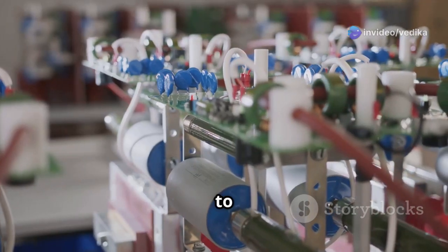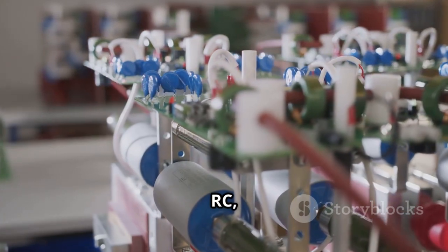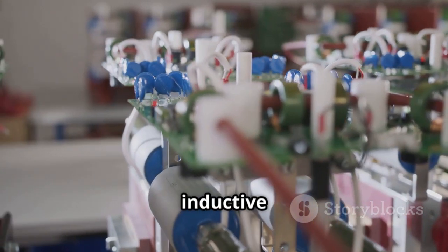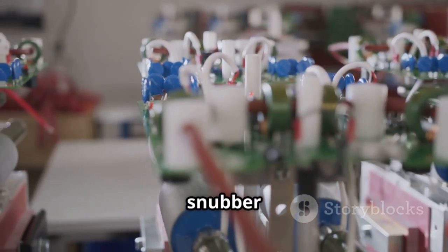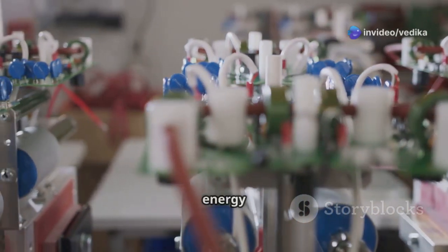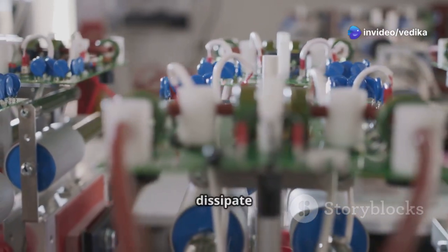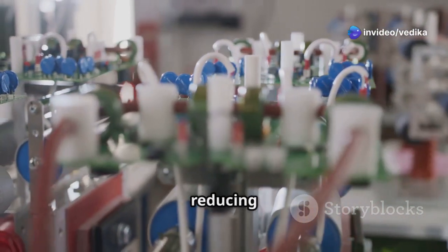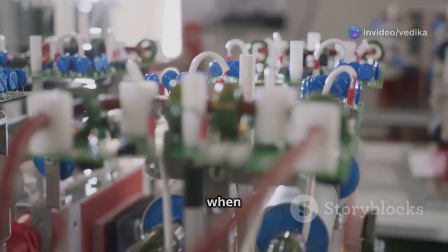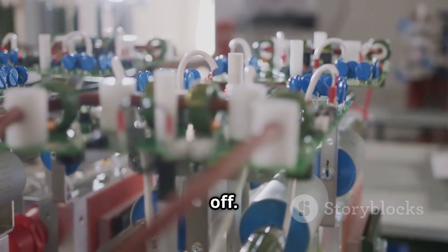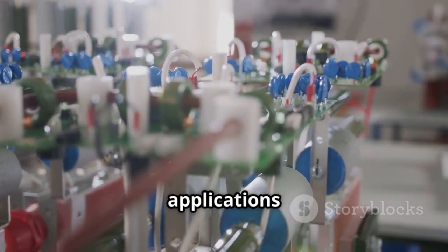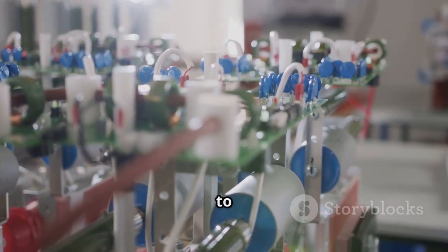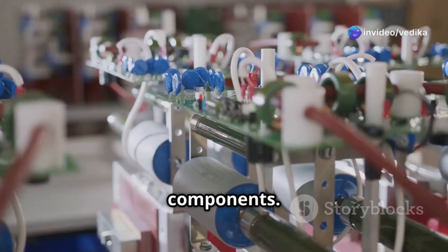One alternative is to use a resistor capacitor, or RC, snubber circuit in parallel with the inductive load. The RC snubber circuit is designed to absorb the energy from the inductive load and dissipate it as heat, thereby reducing the voltage spike that occurs when the load is switched off. This method is particularly useful in applications where the voltage spike needs to be minimized to protect sensitive components.